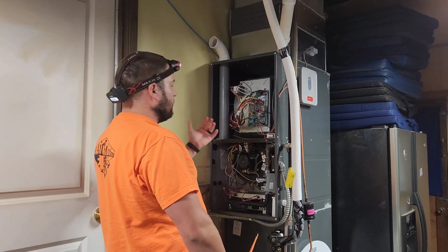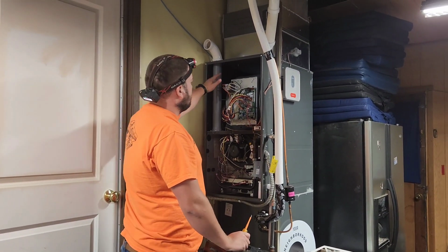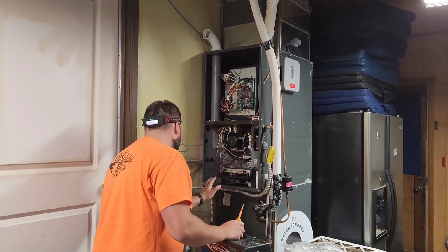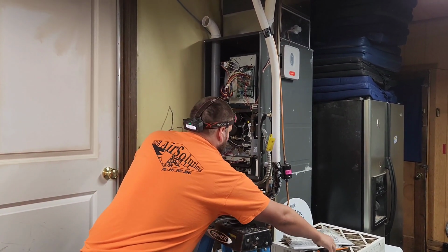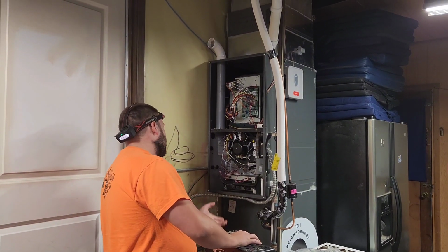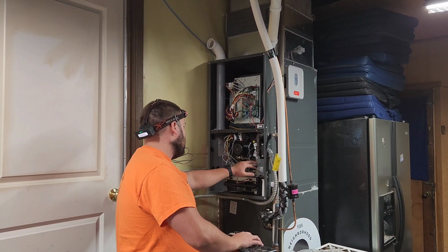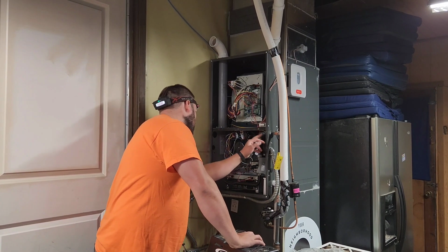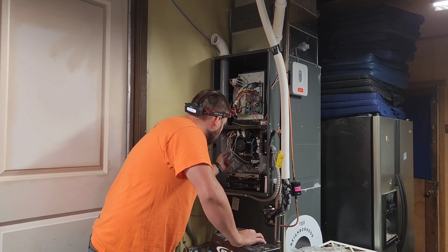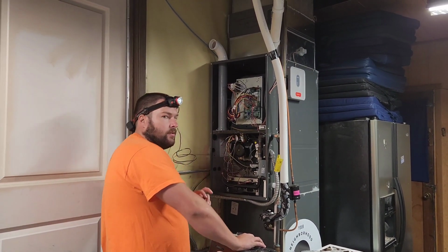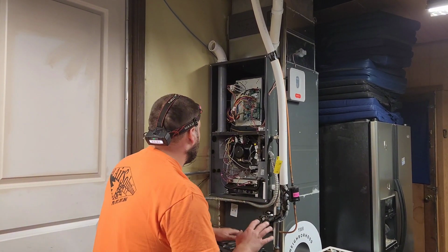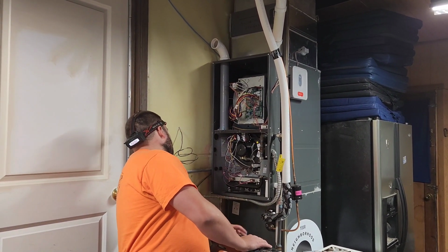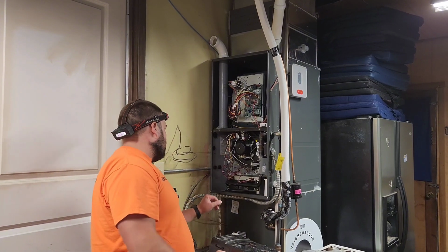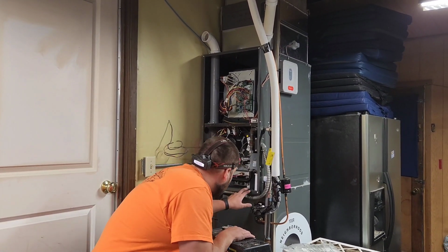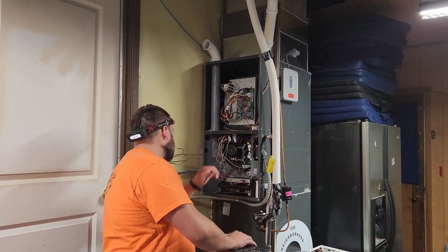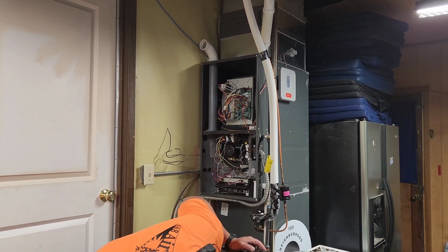Okay, so this is your furnace. You've got 2 compartments. This is your blower motor. This is your burner compartment right here. We start with the burner side, so we'll do a visual inspection, especially of your gas line connections coming in, any loose wiring that might be getting caught in the inducer motor. We'll check all that, as well as a visual inspection on any electrical components, rollout switches, stuff like that.